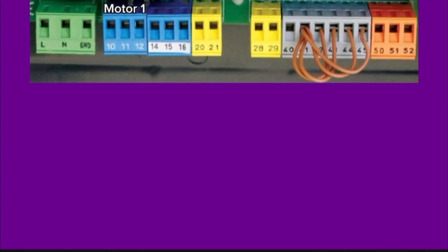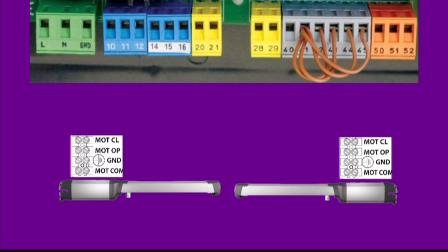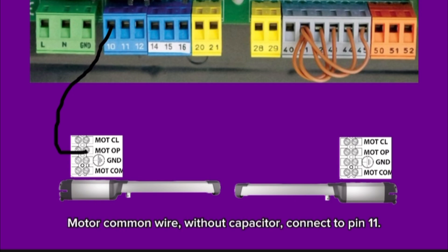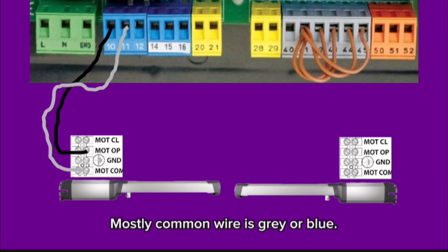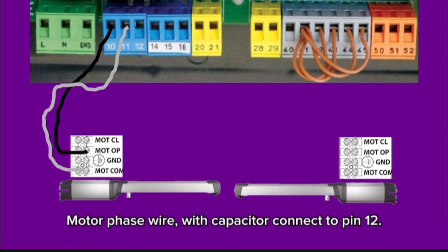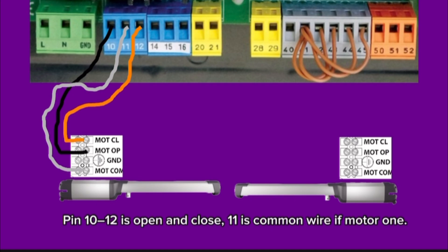Connection of motor 1. Motor phase wire with capacitor connects to pin 10. Motor common wire without capacitor connects to pin 11. Mostly common wire is gray or blue. Motor phase wire with capacitor connects to pin 12. Pin 10 and pin 12 are open and close wires, and pin 11 is common wire of motor 1.